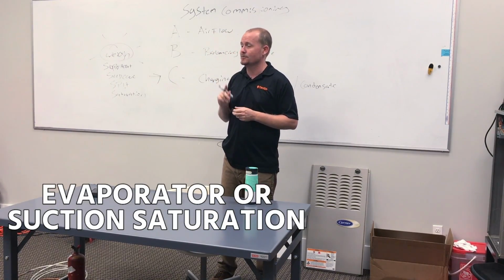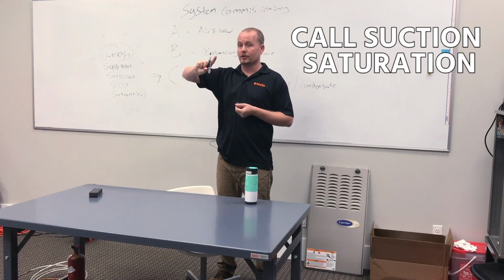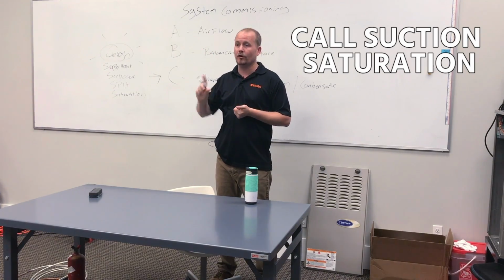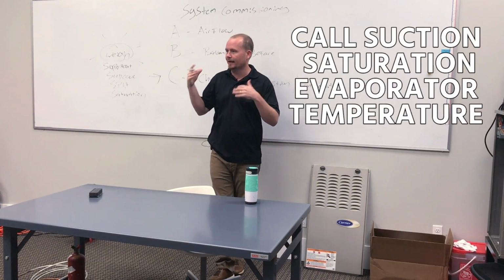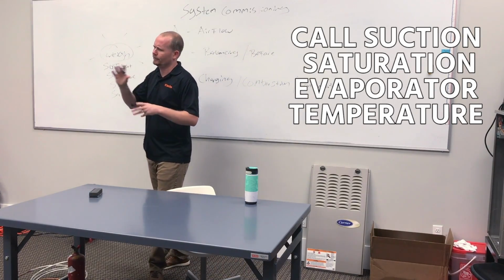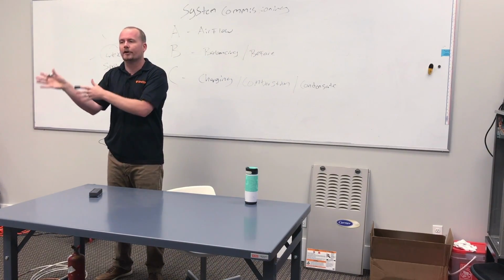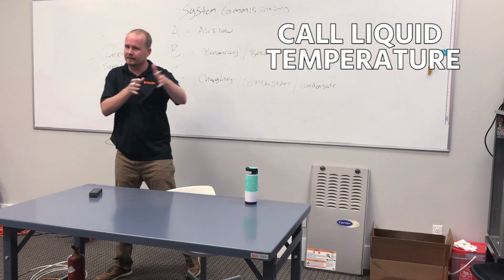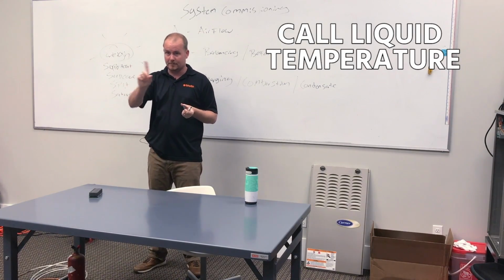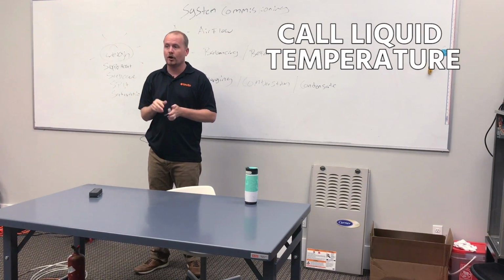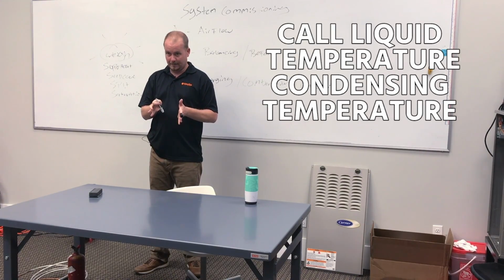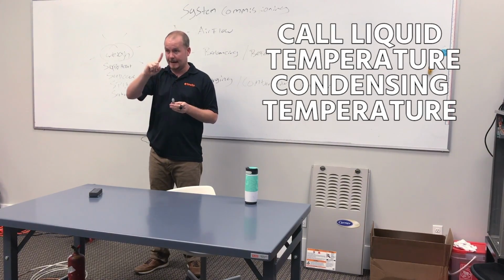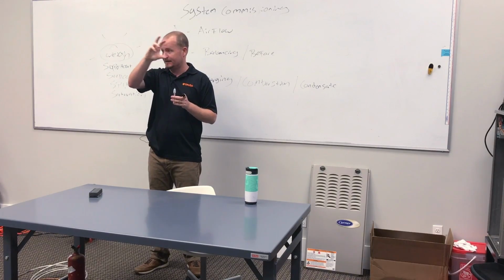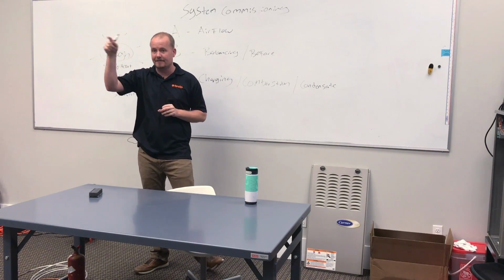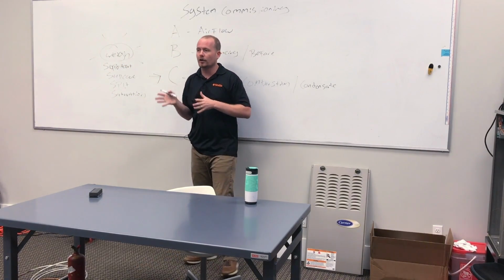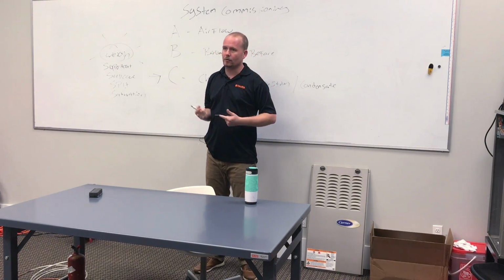Now, I would love it if you would change your language and call your suction saturation, what you see on the gauge, your evaporator temperature. Some people will argue that's not exactly your evaporator temperature because the surface is, forget it. Call it your evaporator temperature, and call the liquid temperature that shows up on the gauge, not the liquid line physical temperature, your condensing temperature. You follow what I'm saying? The needle's pointing at that temperature, or your Testos are showing you a temperature, and I think Testo will even say EV or CO or something like that. Call it that, because it makes it more clear what you're talking about.